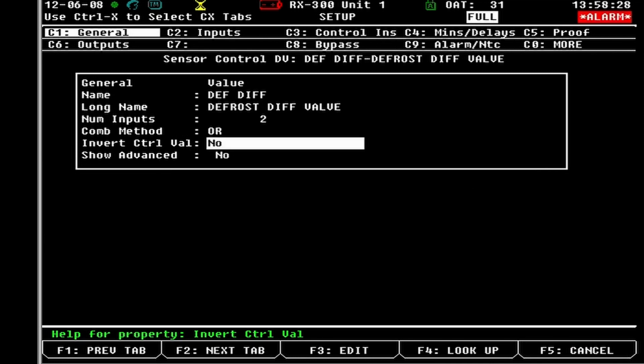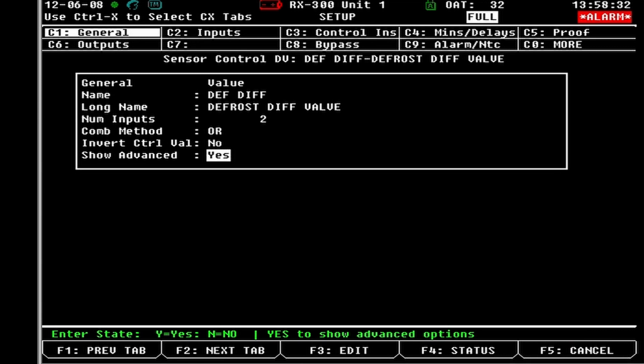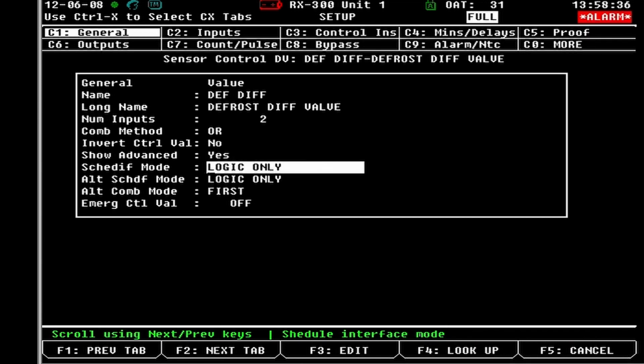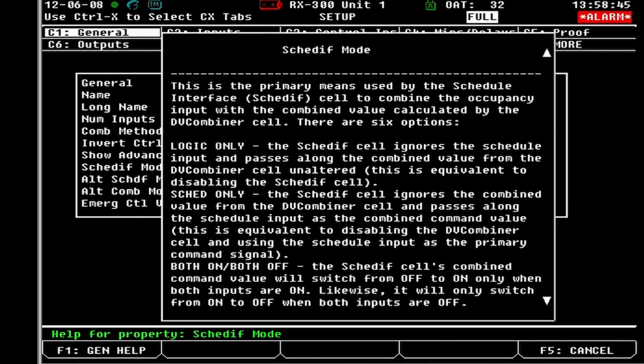It'll do the opposite. So if we go down here, you can go to show advanced. You can click yes, and then you have Schedif mode. This is the primary means used by the schedule interface cell to combine the occupancy input with the combined value calculated by the DV combiner cell. There are 6 options. Logic only: Schedif cell ignores the scheduled input and passes along the combined value from the DV combiner cell unaltered. This is equivalent to disabling the Schedif cell. Schedule only: Schedif cell ignores the combined value from the DV combiner cell and passes along the scheduled input combined command value. This is equivalent to disabling the DV combiner cell and using the scheduled input as a primary.